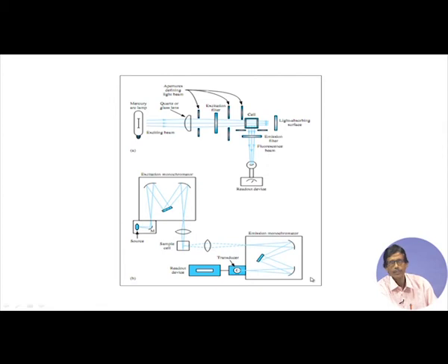This is the basic difference from our absorption spectrometer or FTIR spectrometer: we have two monochromators, one excitation monochromator and another emission monochromator. With the excitation monochromator we can monitor the excitation wavelength, but the light also falls on the sample, the sample is excited and emits radiation at right angle, and the transducer manages the emission, which goes to the detector and ultimately to the readout device.